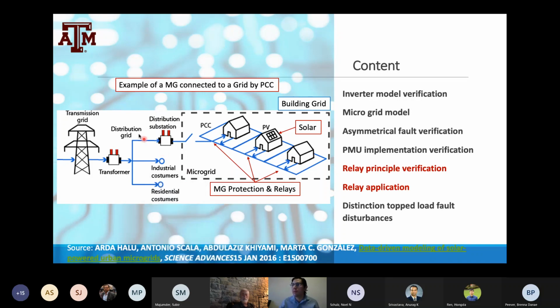So basically, following up Professor Miroslav Begovic's presentation, I will talk about this example of how a microgrid is connected. The content I will cover today includes inverter model verification, microgrid model, asymmetrical faults, PMU verification, some relay principles and applications that we will address specifically for our case studies, and the distinction between kinds of faults and kinds of loads that can create confusion as to whether the grid decides it is a fault or not. So here in the figure you can see the critical part of the model.